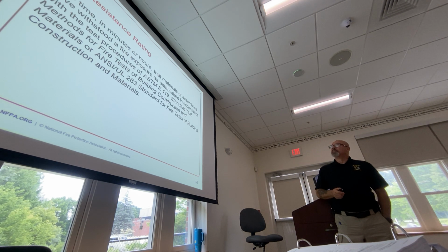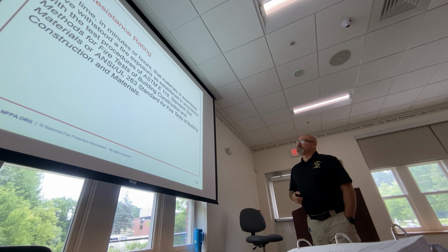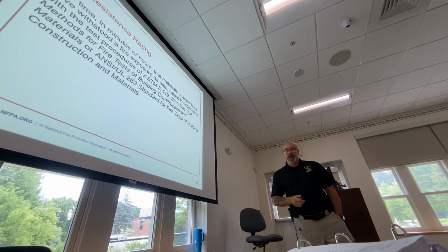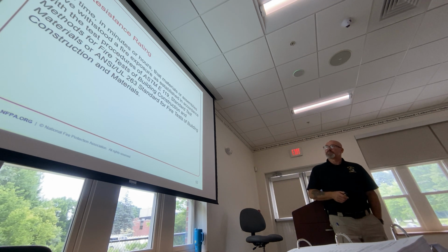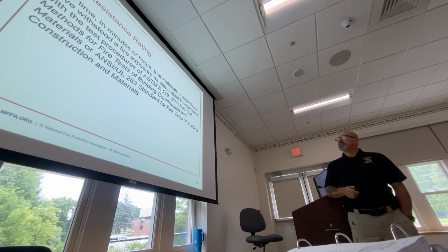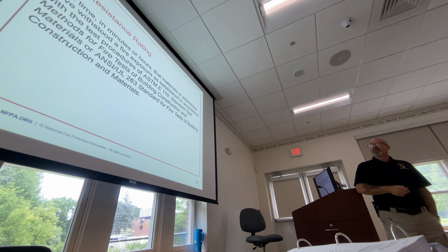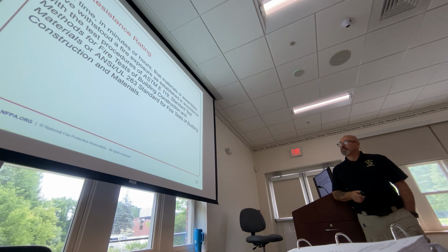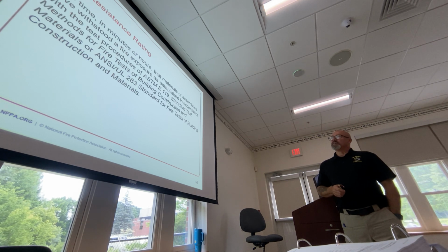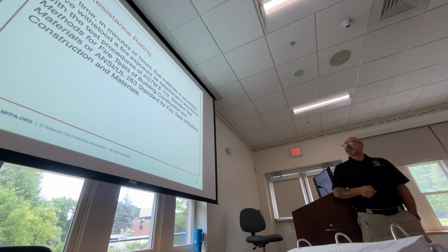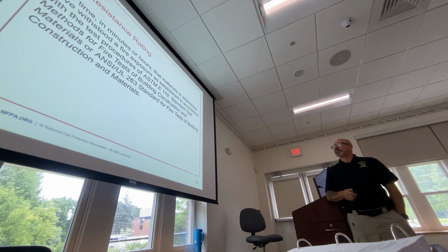It's the time in minutes or hours that materials or assemblies have withstood fire exposure as established in accordance with test procedures of ASTM E119, Standard Test Methods for Fire Tests of Building Construction and Materials, or ANSI UL 263, Standard for Fire Tests of Building Construction and Materials.